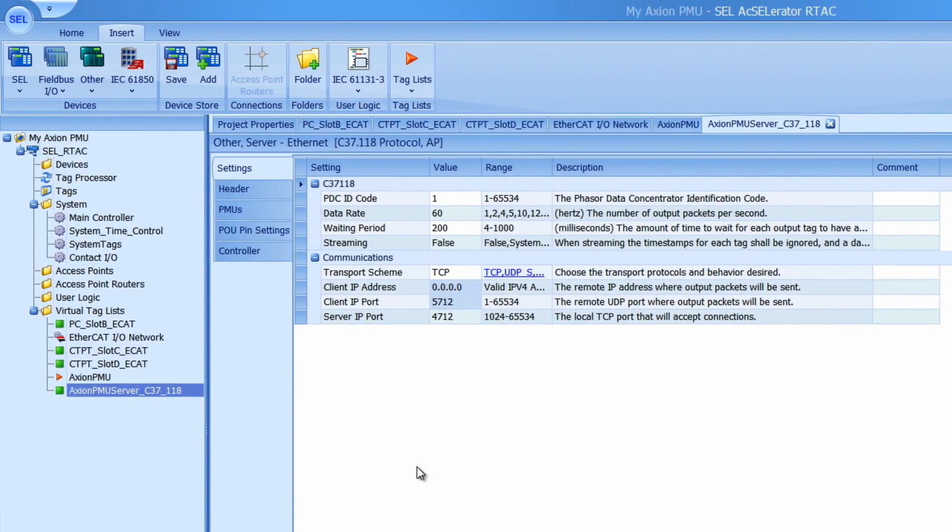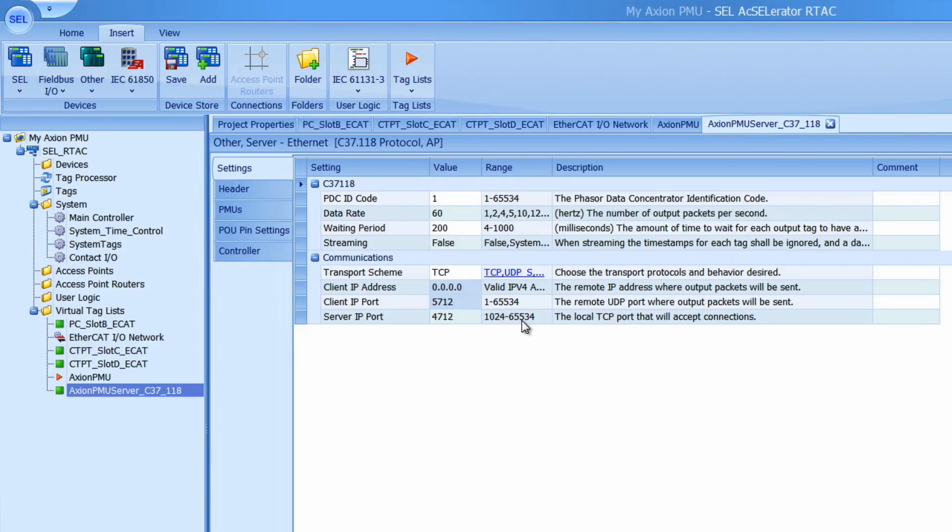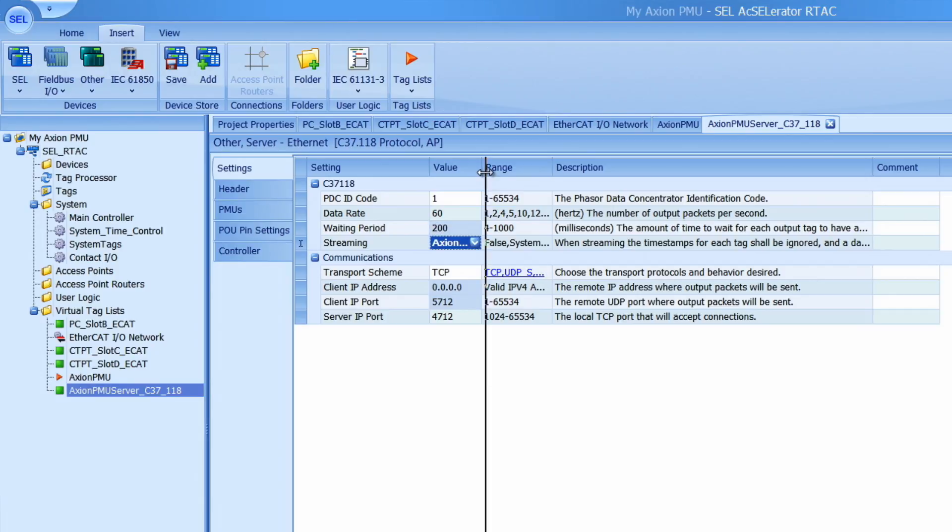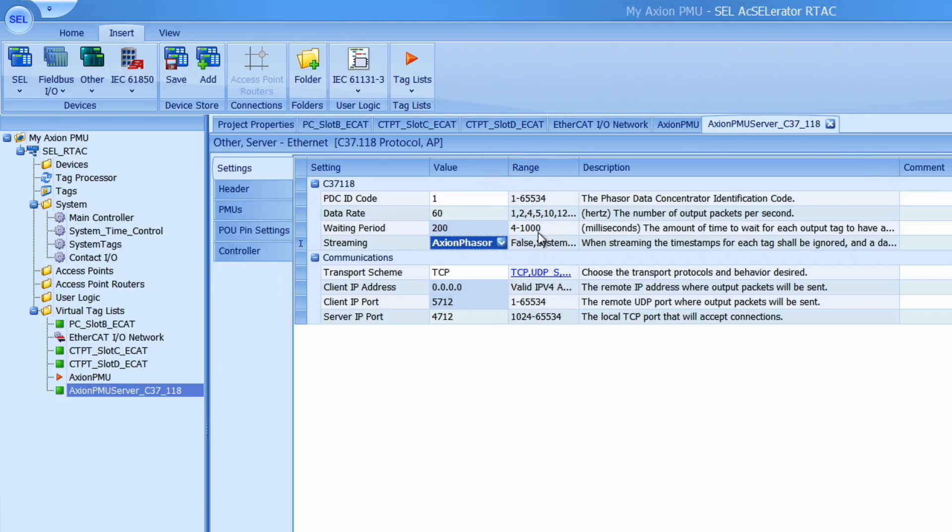Okay now we can configure our server. In the settings tab you will have to configure the proper protocol and communication parameters. If you are only using phasor quantities from the Axion AC metering modules like we are in this case, change the streaming mode to AxionPhasor. I'm going to leave the rest of these settings. But for your application make sure you have the correct PDC ID code data rate as well as transport scheme port number etc. So that your client can connect to the server.